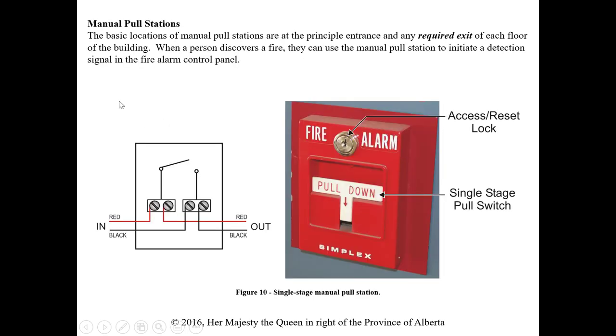Manual pull stations must be located at the principal entrance and any required exit, with the required exits determined by the classification of each floor. When a person discovers a fire, they use the pull station to initiate a detection signal at the fire alarm control panel. Pulling it down basically closes a switch, providing an alternative path for current flow instead of through the end-of-line resistor — it shorts out the device and puts the system into an alarm condition.